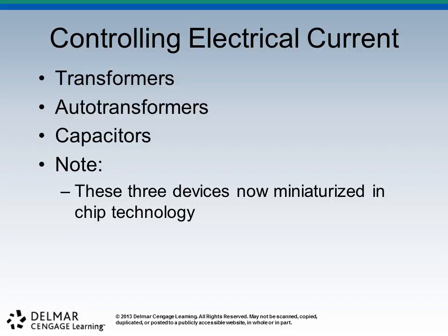And inside our X-ray circuit, we've got various things in here, and you'll see there's a couple of them listed here: transformers and auto transformers. We'll also talk about capacitors, but as a separate power supply. Transformers, the job of the transformer, if you see on page 76, is to change the current. It's going to make the current, in our case, increase or decrease in voltage. And for us in X-ray, we do both.